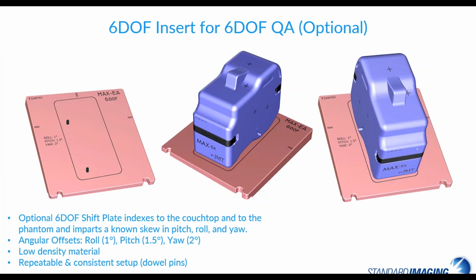As far as the 6 DOF QA that you can use with the Max EA, we have the 6 DOF plate, which is optional. So the 6 DOF plate indexes to the couch top and to the Phantom. So it does impart a known skew in pitch, roll, and yaw. You can see there we have angular offsets of roll at 1 degree, pitch at 1.5, and yaw at 2. It's made of a lower density material, and it also allows for repeatable and consistent setup, again with the dowel pins.